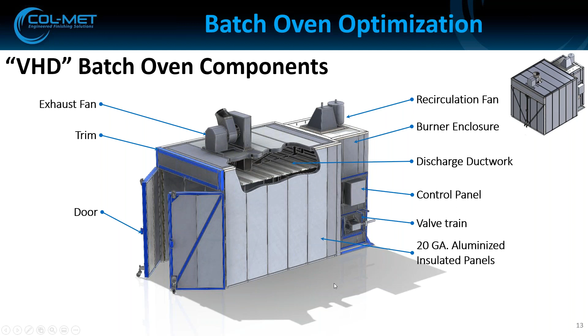For this unit, though, there is some assembly required on the burner enclosure. Basically the burner comes mounted and pre-tested on a frame, then you just have to install the panels on it. But other than that, the two ovens are very similar, with many of the same features as far as temperature range. Mainly the differences are the options on where the heater box can be located. With the BO oven, since the ductwork is in the side, we have more flexibility on where we can locate the heater box. In some instances it doesn't matter where the heater box is, but in others, if there are issues with floor space or access based on some obstruction, it might be a critical consideration.